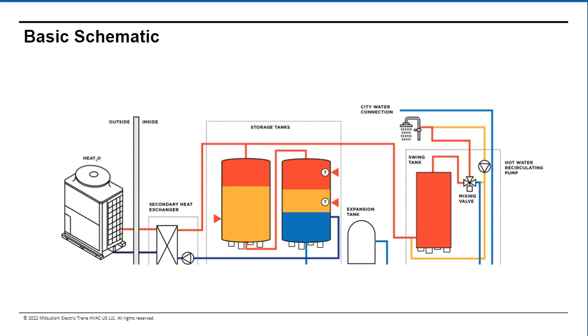This is typically done to protect the heat exchanger inside the hot water heat pump, since the secondary heat exchanger is relatively inexpensive. There is a secondary pump on the other side of the heat exchanger to circulate domestic hot water to the storage tanks. The storage tanks contain sparge systems that reduce the water velocity to 4 feet per minute or below in order to get good stratification in the tanks, so that the return water to the hot water heat pump is as cold as possible, which maximizes your COP efficiency for the system.